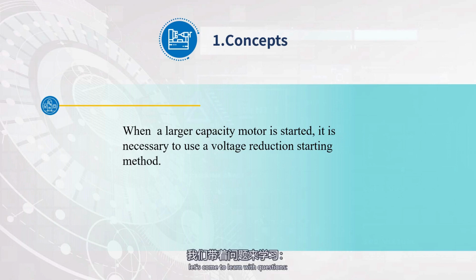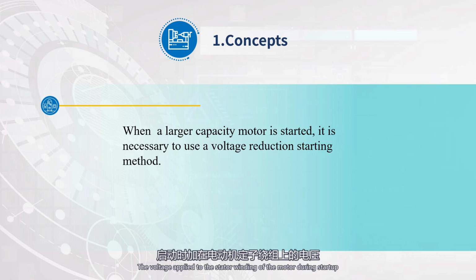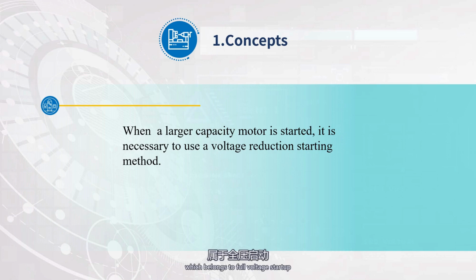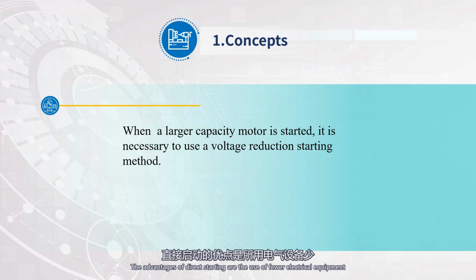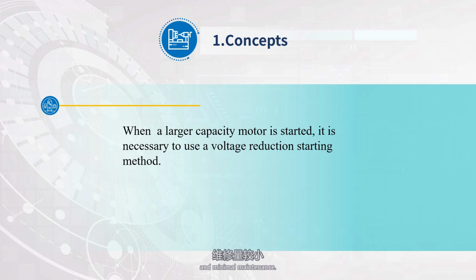Next, let's come to learn with questions. The voltage applied to the stator winding of the motor during startup is the rated voltage of the motor, which belongs to full voltage startup, also known as direct startup. The advantages of direct starting are the use of fewer electrical equipment, simple wiring, and minimal maintenance. But when starting directly, the starting current is relatively high, usually 4 to 7 times the rated current.